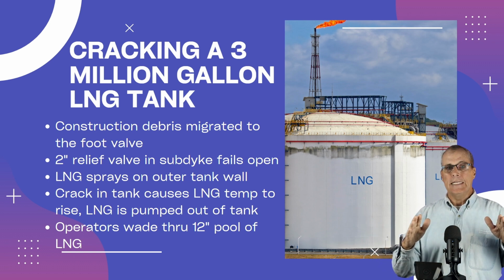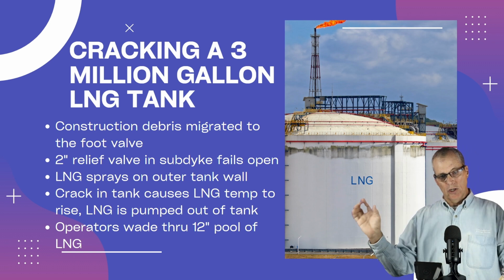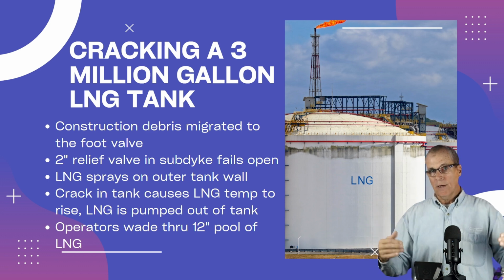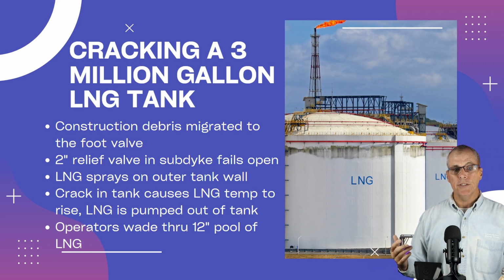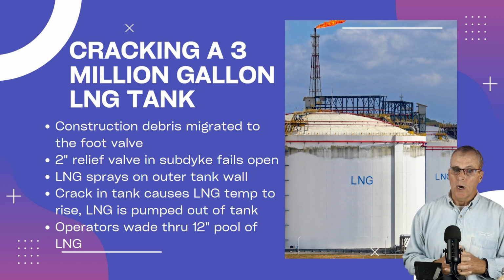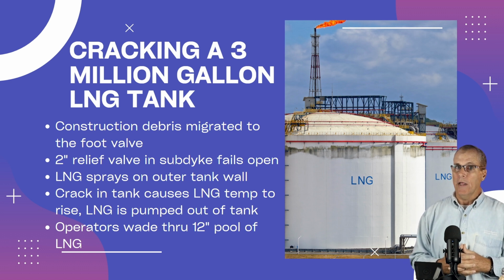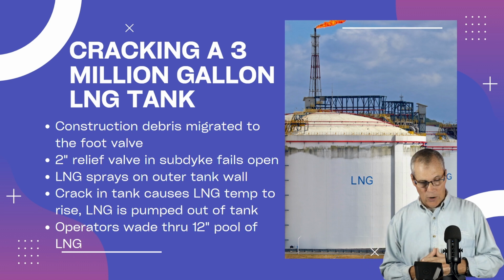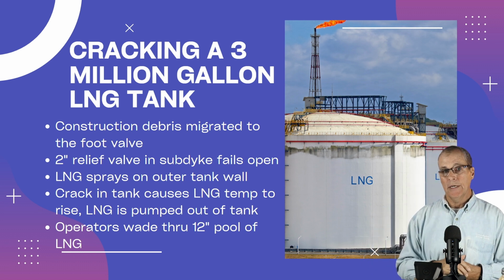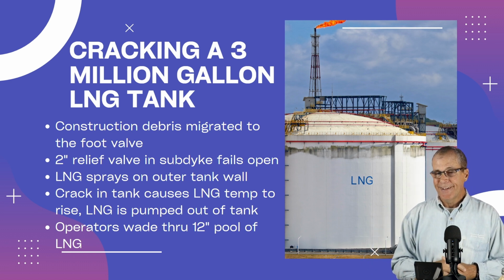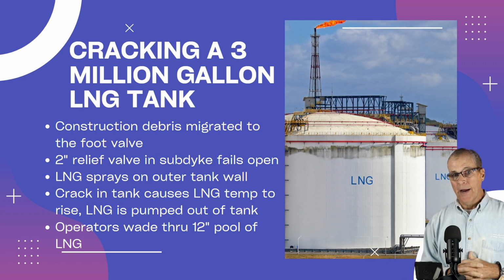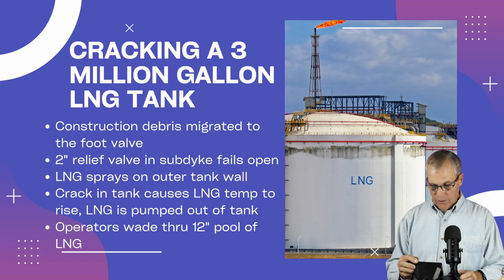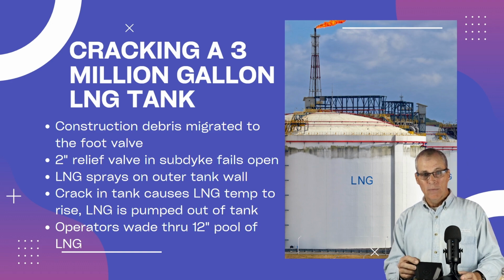Warm air was starting to get inside the LNG tank in that interstitial space, but it was warming up the LNG, so the boil-off rate started to increase. Eventually, we were able to get that relief valve shut. Nobody got hurt. Fire department showed up and basically asked if we needed any help. We didn't, and they left. Nobody got hurt, no explosions, no fires, but very near disaster in downtown Baltimore.